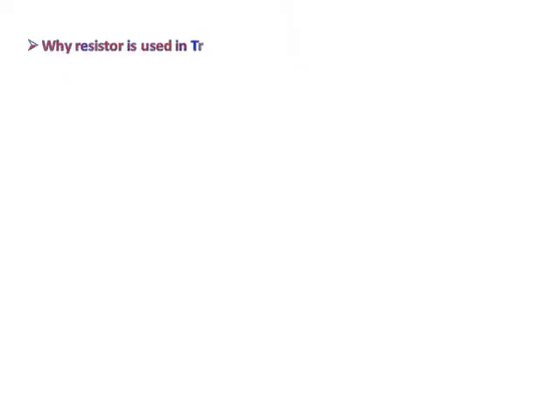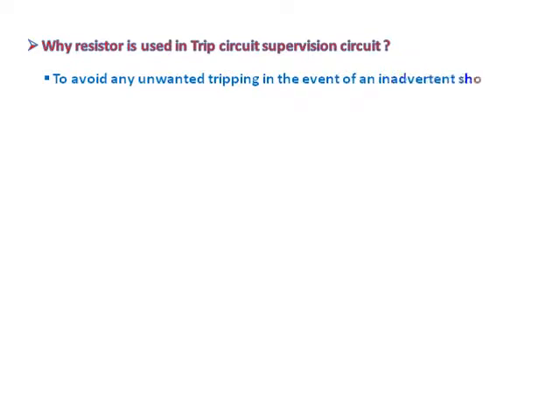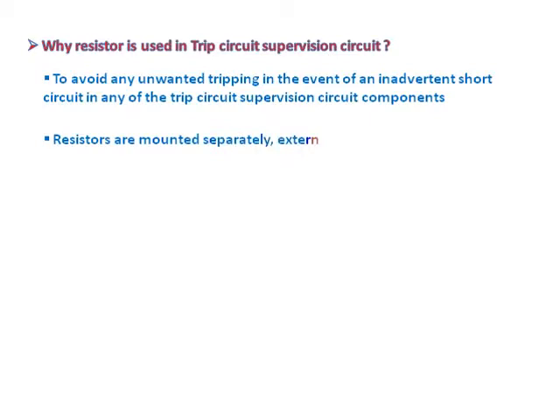Why is a resistor used in the trip circuit supervision circuit? To avoid any unwanted tripping in the event of an inadvertent short circuit in any of the trip circuit supervision circuit components. Resistors are mounted separately, external to the relay, and are added in series with coils A, B and C.